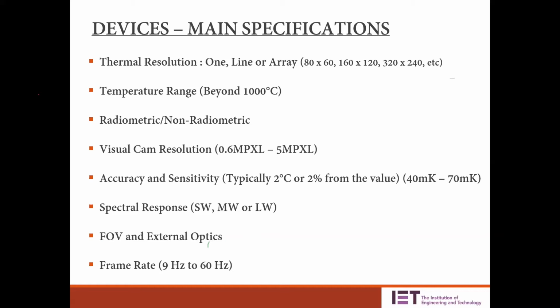accuracy, meaning that you cannot use your industrial thermal imager, used in the factory, to measure the temperature of your personnel. You cannot use it as a fever screening device. However, some of the imagers have a special module inbuilt for elevated body temperature scanning. That mode will provide an improved accuracy of up to 0.2 degrees Celsius. If you have that EBT module inbuilt, you can use it as a fever screening camera.